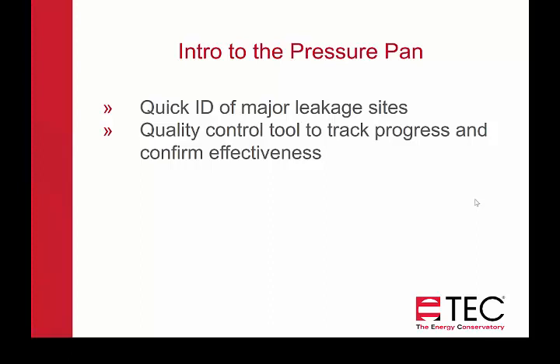It can be used as a quality control tool to track the progress and confirm the effectiveness of your work. In some cases you'll have one register with a really high number, and that will affect all your other numbers also. You can seal one, two, or three ducts and get all of the numbers down. Tracking your progress — starting the blower door up again as you're sealing — can really speed things up and confirm that you're making progress. When all the numbers are low enough, you can do a duct blaster test and confirm that you've got the amount of reduction you're hoping for.